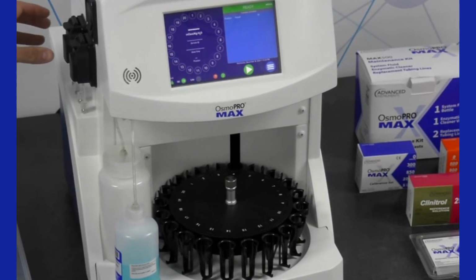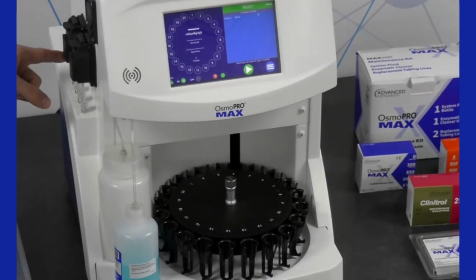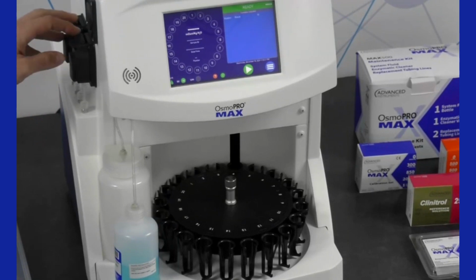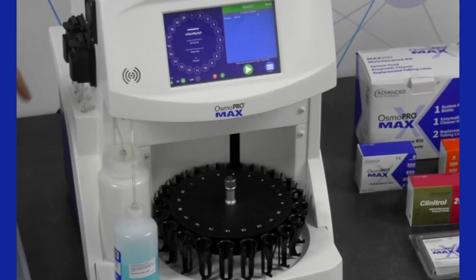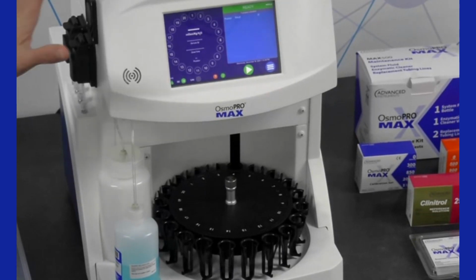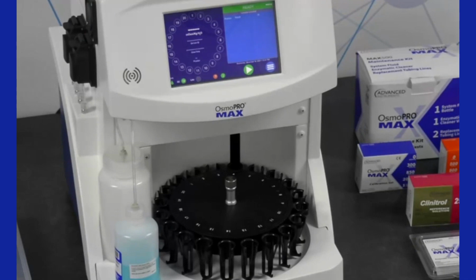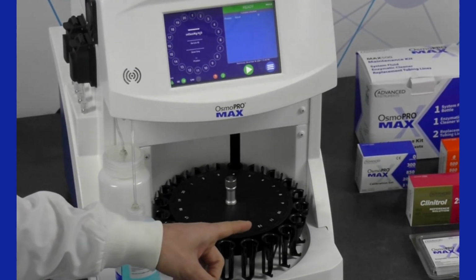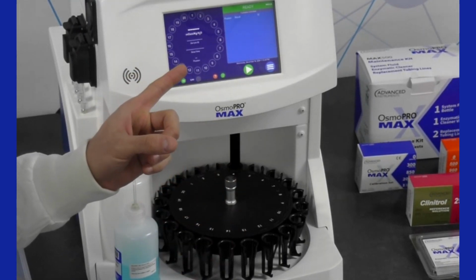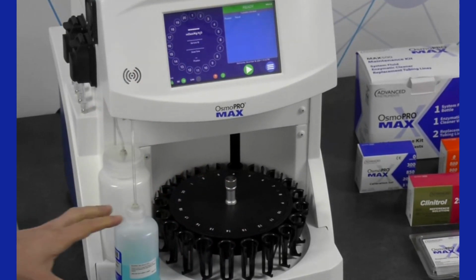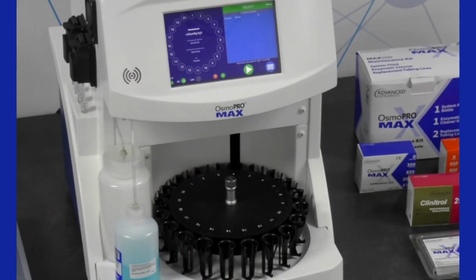Over here on the side, you'll see these little black covers. That is where the peristaltic tubing and the peristaltic pump are housed. This is actually the mechanism that pumps the system fluid through the instrument. So the OsmoPRO Max is unique in our line of osmometers in that it relies on flow-through technology to deliver the sample to the sample chamber where the freezing point depression measurement takes place. And then, of course, we have system fluid on board to wash any of that sample out and into that waste container.